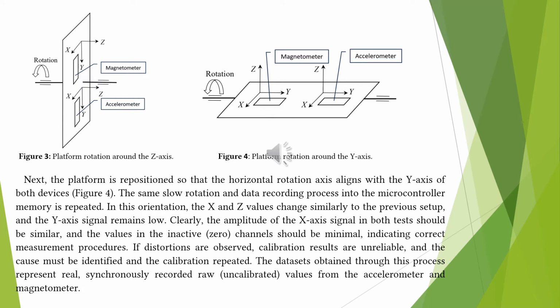The sensor platform is mounted onto a rotating device with axes aligned as shown in Figure 3. A slow rotation is performed with a set increment around the horizontal axis, which corresponds to the z-axis of both devices. The microcontroller periodically captures readings from both the accelerometer and magnetometer. In this configuration, the x and y components of the accelerometer vector change, while the z-axis reading remains low, primarily determined by the offset of the z-axis channel.